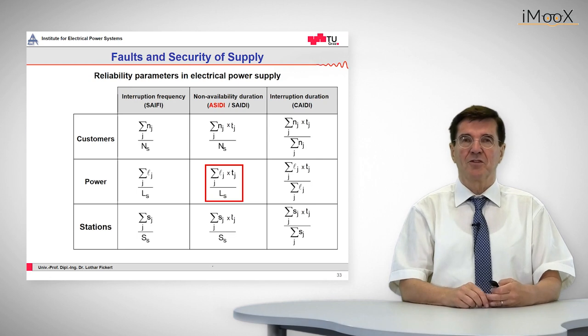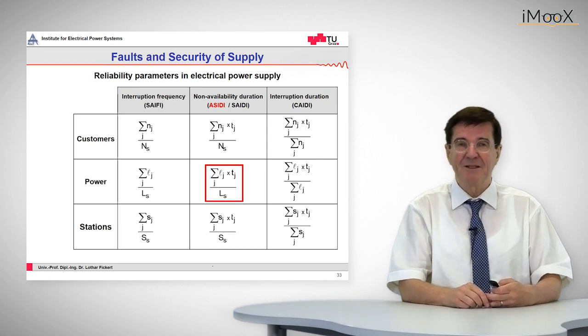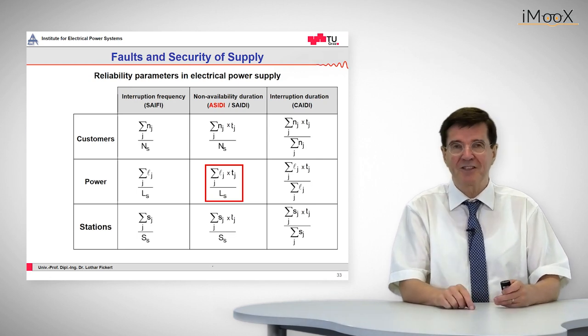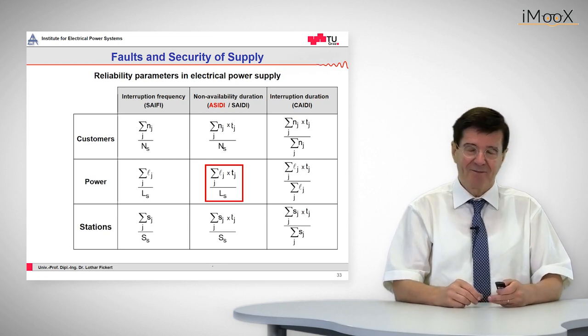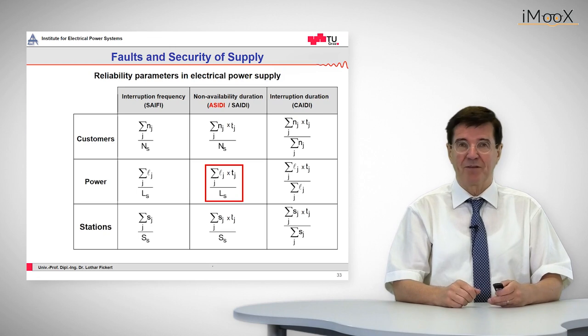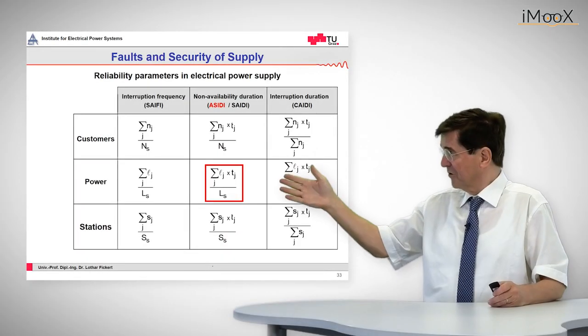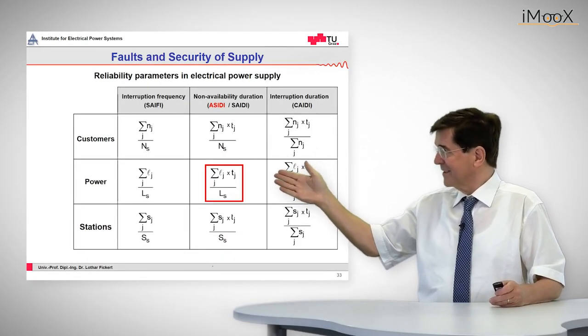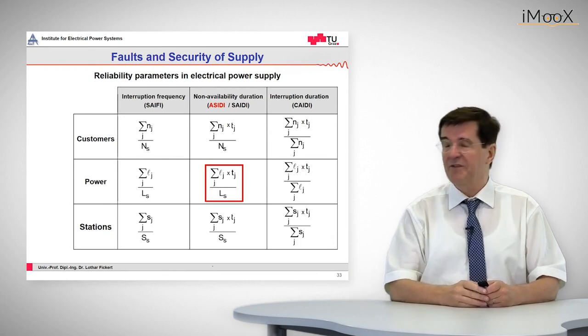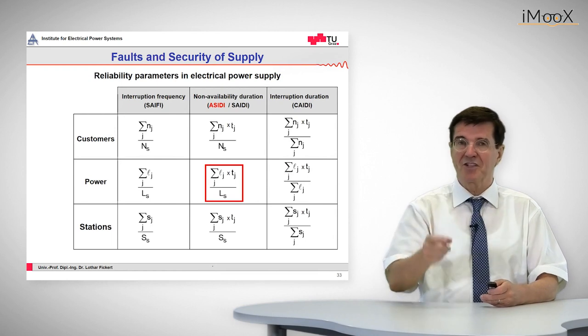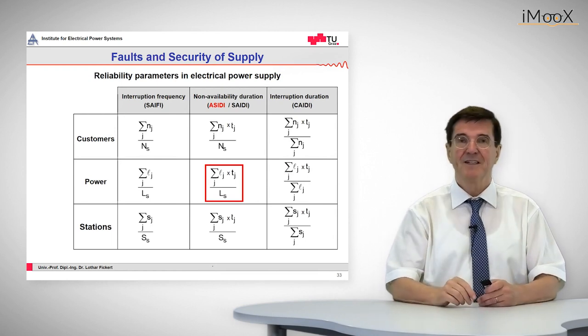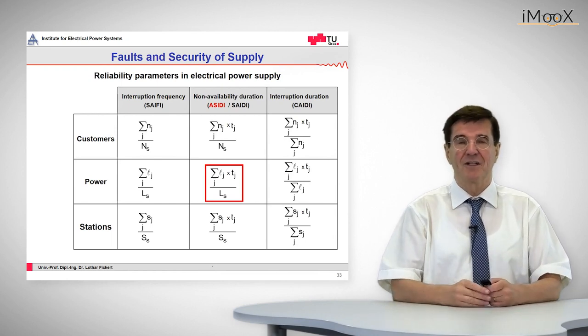How do regulators measure and take care of these protection functions? That is done by the so-called ASIDI figure: Average System Interruption Duration Index. That means a weighted outage time, where weighting is done by the power not supplied. This ASIDI figure is given by the product of the power and the outage time, which is the energy not supplied.